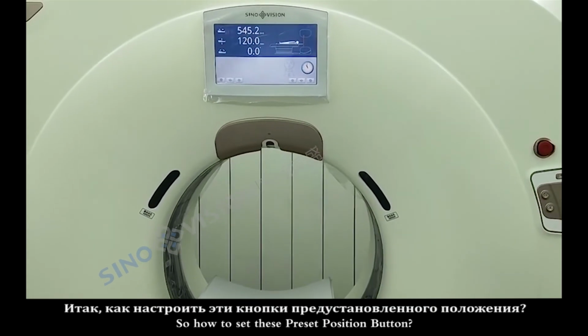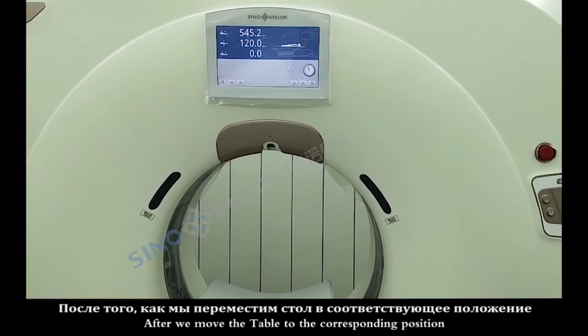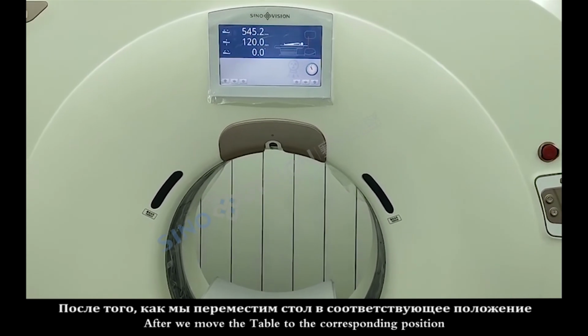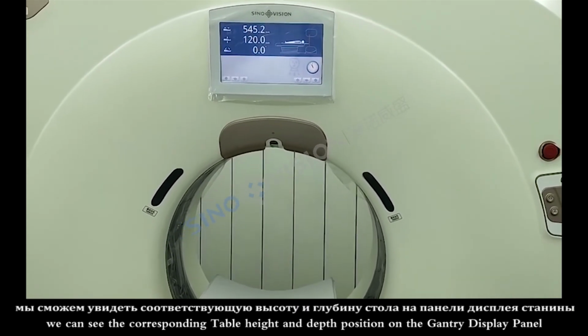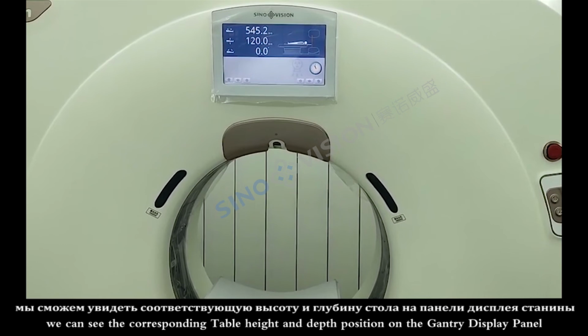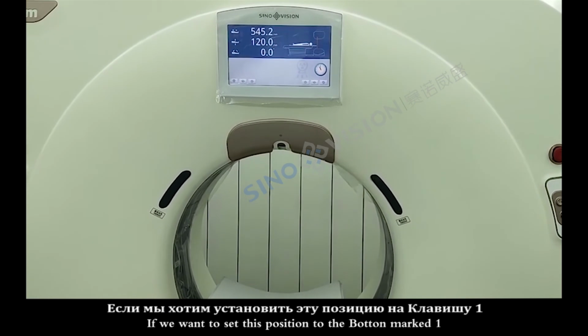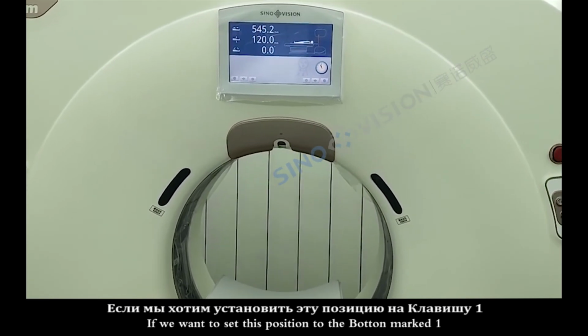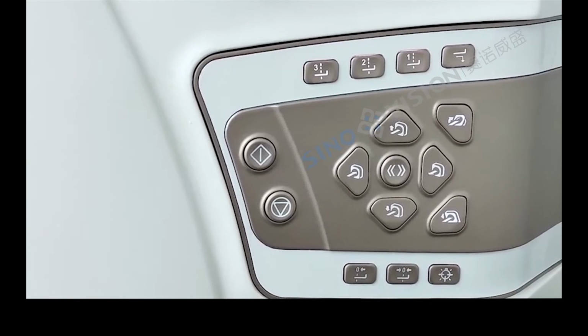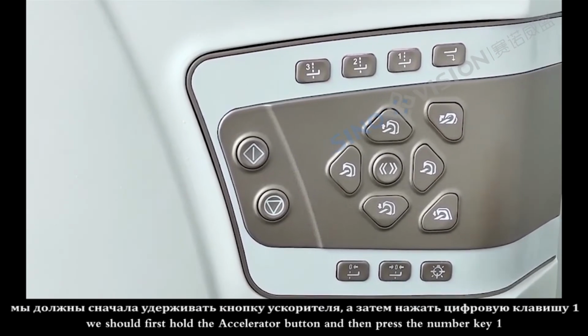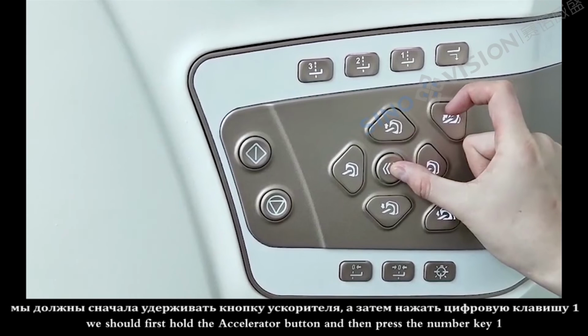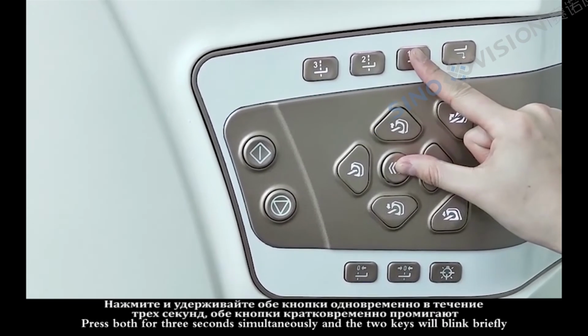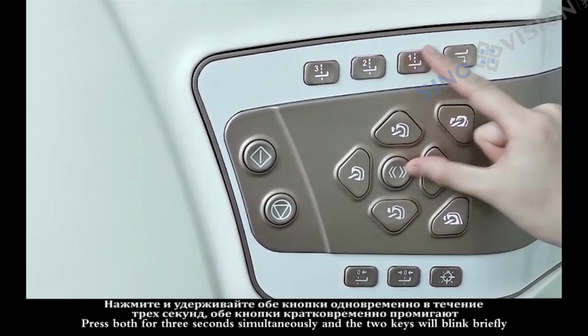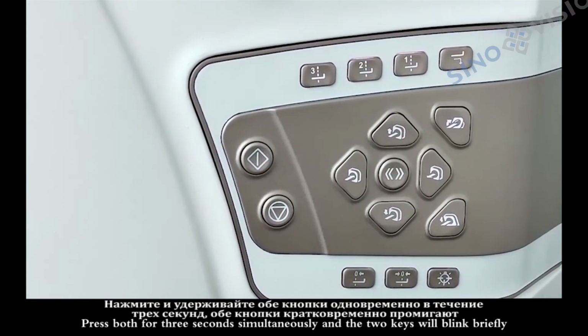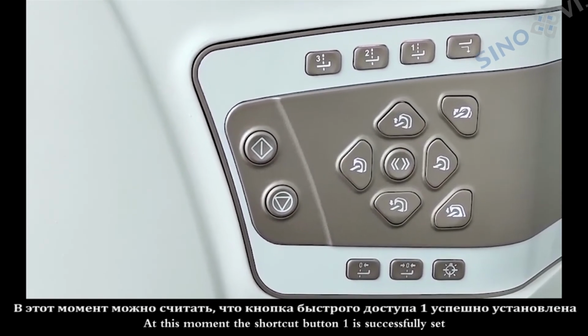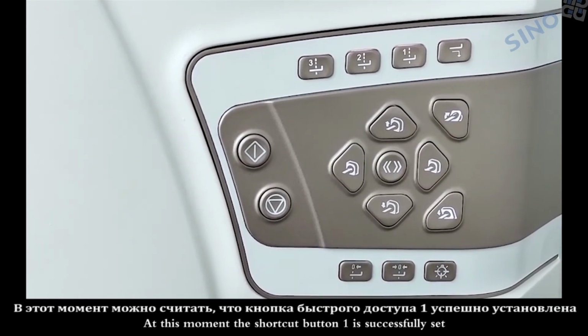So how do you set these shortcut buttons? After we move the table to the corresponding position, we can see the corresponding table height and depth position on the gantry display panel. If we want to set this position to the preset position shortcut button 1, we should first press the accelerate button, and then press the preset position shortcut button 1. After 3 seconds of simultaneously pressing them, you can see the two buttons blinking briefly. At this point the shortcut button 1 is successfully set.